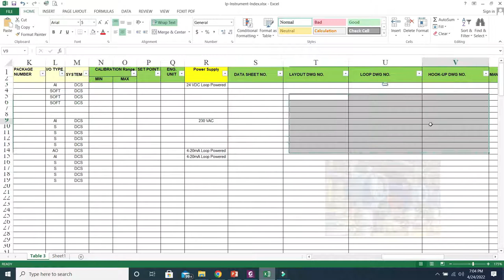Again, the data sheet number, layout number, loop drawing number, hookup drawing number. These are the document numbers which we need to provide for each and every physical instrument item. So whenever we track any particular instrument, just like if we want to quickly open the loop drawing of this level transmitter V30301, how will we go to that particular document? We can find this document from the instrument index, go to that particular document and see the loop drawing. So data sheet, layout, loop drawing number, hookup drawing number, these drawing numbers we will also update whenever our DCI, document control index, is ready accordingly.